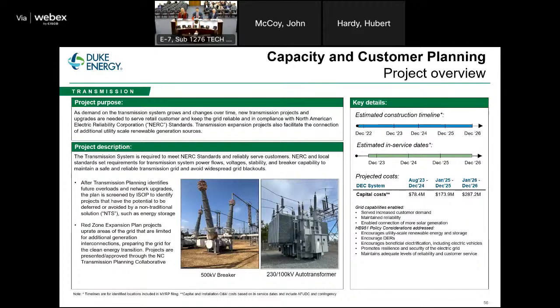And many of our projects are driven by these planning studies, right, which identify the need for capacity upgrades, redundancy in some cases. Sometimes we can have redundant relays or breakers that we can actually put in. So we are looking for the most efficient solution, if you will, to a problem that's identified through a planning study. I mentioned those capacity upgrades are informed through the ISOP process. So if we do identify a need to upgrade a substation or say upgrade a transformer, that may be driven by a peak load condition that occurs during a very small window of time, summer, middle of the day, highest load time. That is where we have a constraint. So for this reason, we are looking at what's the most efficient way we can address that constraint.